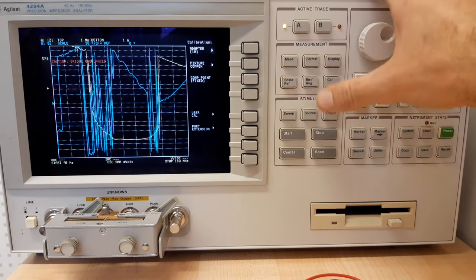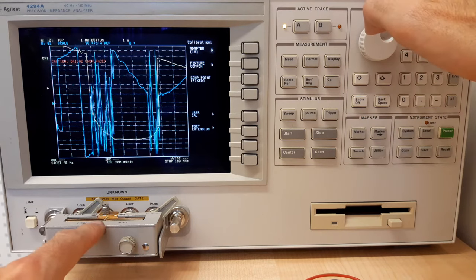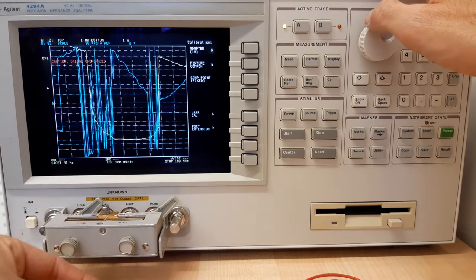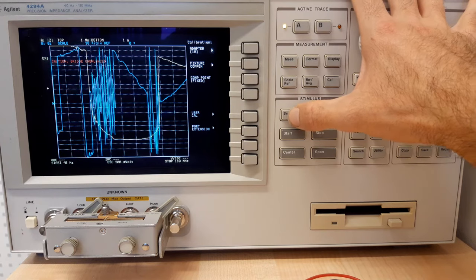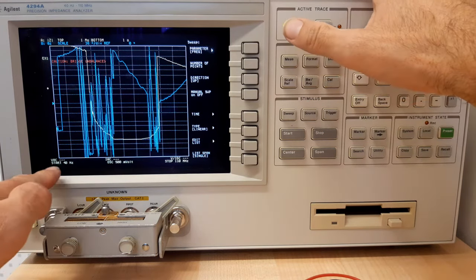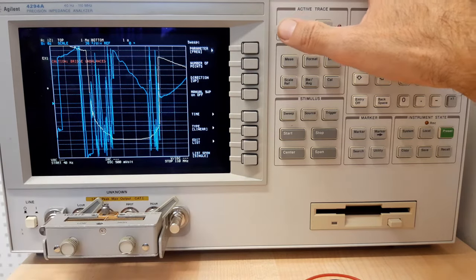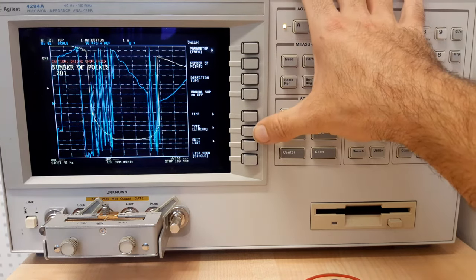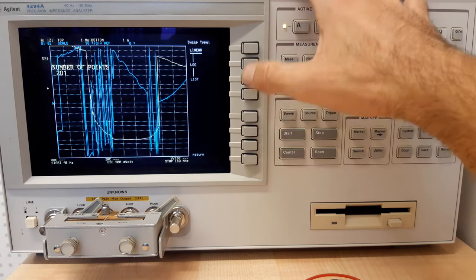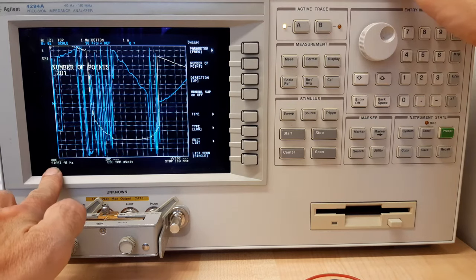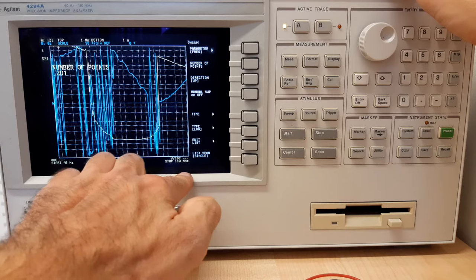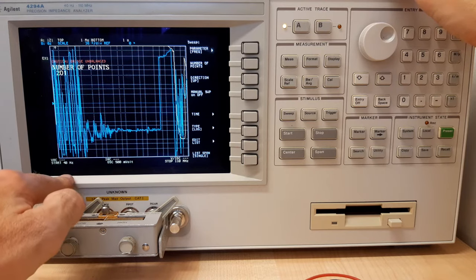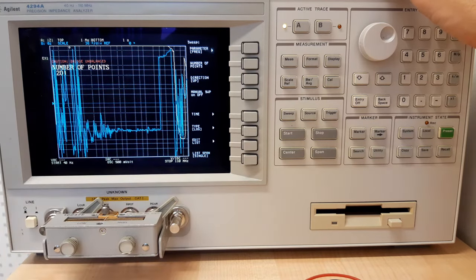Now we set the stimulus — the source. The instrument applies a voltage and pushes current through the device under test, for example this resistor. Under the sweep button, it sweeps through frequencies from 40 Hz to 110 MHz with 201 points. We'll switch the sweep type from linear to logarithmic, so it sweeps in logarithmic steps from 40 Hz to 110 MHz — putting more emphasis on low frequencies and sweeping faster through higher frequencies.